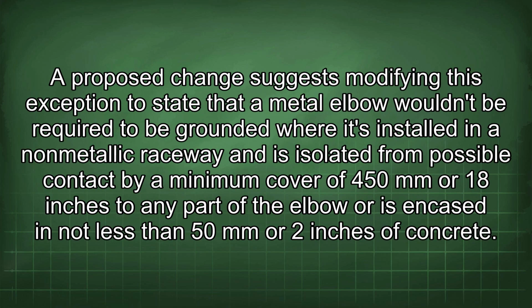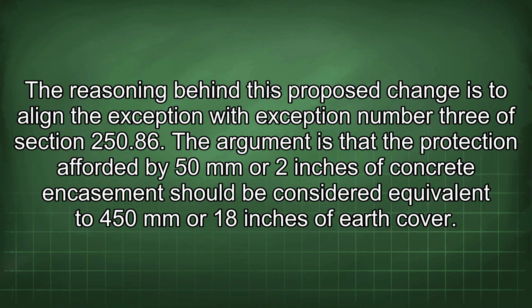A proposed change suggests modifying this exception to state that a metal elbow wouldn't be required to be grounded where it's installed in a non-metallic raceway and is isolated from possible contact by a minimum cover of 450 mm or 18 inches to any part of the elbow or is encased in not less than 50 mm or 2 inches of concrete. The reasoning behind this proposed change is to align the exception with exception number 3 of section 250.86. The argument is that the protection afforded by 50 mm or 2 inches of concrete encasement should be considered equivalent to 450 mm or 18 inches of earth cover.